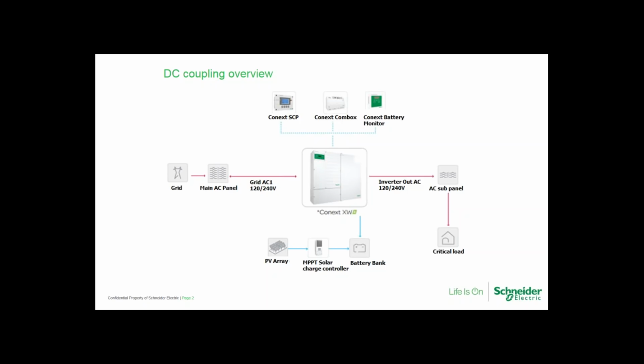So the grid support voltage setting is the level at which you want to hold the batteries. When you're operating in grid support mode, you can either set the grid support voltage at the float level or a little lower, or if you're using our charge controllers, we have a feature called enhanced grid operation. We'll talk about that a little more in the next slide.